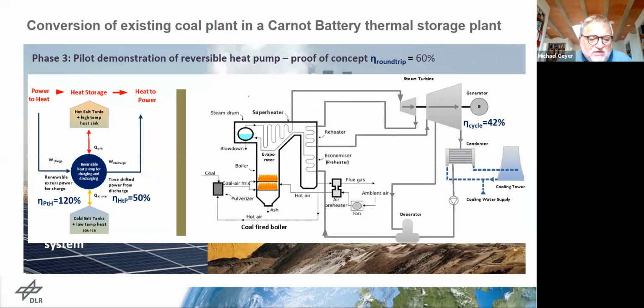The big advantage is that you can do this at many hundreds of megawatts for many hours, with systems designed for a 35-year lifetime. In future, the ideal storage system would use batteries for short-term grid frequency control, from 15 milliseconds to about 30 minutes — batteries are unbeatable there. But for longer-term storage, these systems, which I call Carnot batteries, will become more cost efficient.